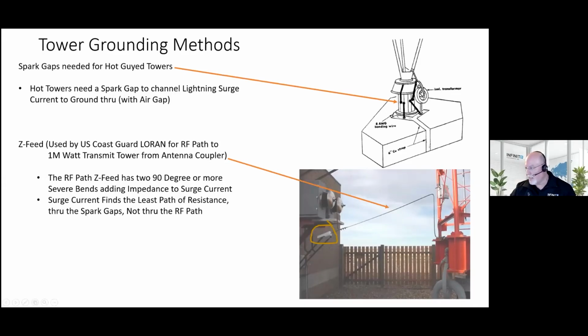I was not a LORAN tech. I was the shipboard electronics guy, but I worked with guys who were in this field, and they described what they called a Z feed. And what that is, this is your antenna coupler building. And so this is the RF path getting to the top of the tower, top of the insulator. And what they've done is they've bent it in two different 90-degree bends here to make this a sour path for the surge current when the tower gets hit, or from induced surge current.